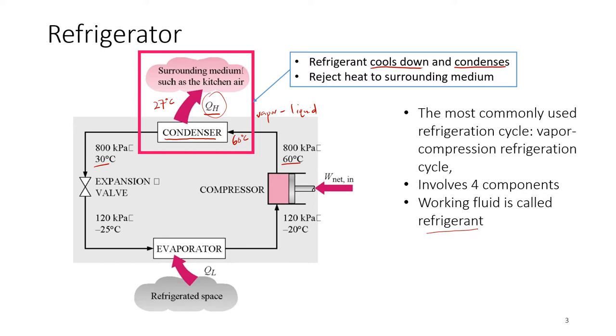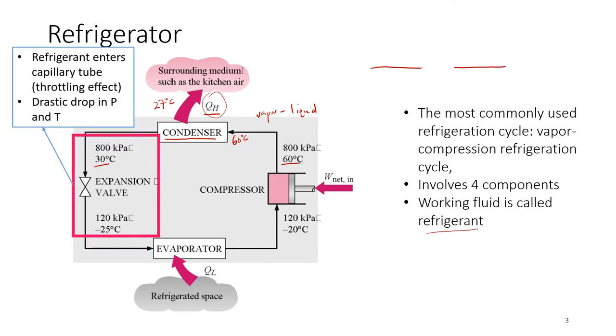As it leaves the condenser, it enters the expansion valve. What happens in the expansion valve? It's like a capillary tube with a throttling effect — you can refer to our notes in chapter 5. What happens here is a drastic drop in pressure and temperature. It loses some temperature after the condenser, but it's not enough — we want it to be colder. So 800 kPa becomes 120 kPa, and 30 degrees becomes negative 25 degrees Celsius.